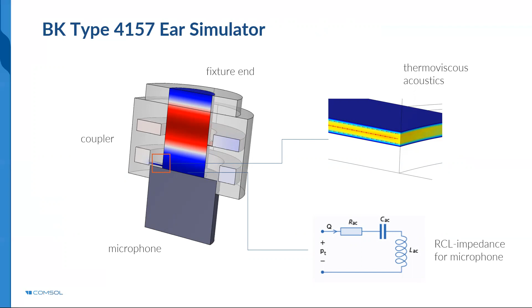In the slits, the very narrow slits that connect the main volume to the side volumes, you need thermoviscous acoustics to capture the losses correctly. The dimensions of the slits and the side volumes define the damping that allows the coupler to mimic the ear canal and eardrum system. So these slits have been introduced in the design of this ear simulator in order to introduce some damping that is the same damping that is associated with the human ear. So that's why the coupler can be used as a standardized ear. So thermoviscous acoustics is used in these narrow slits here.